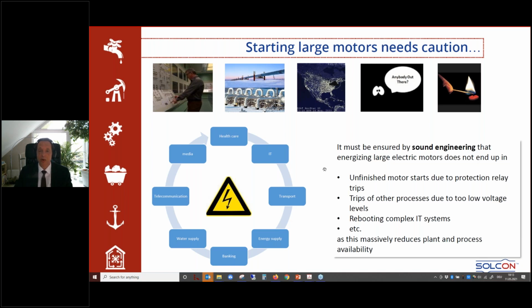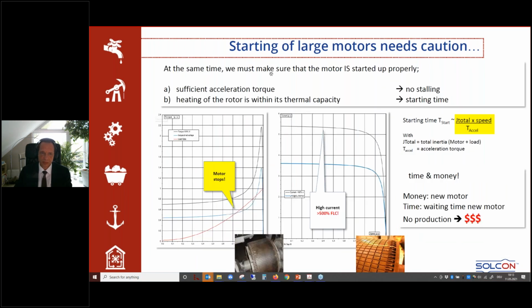So what we need to do, we need to apply sound engineering that we avoid unfinished motor starts due to protection relays tripping. We must avoid that processes are being tripped due to too low voltage levels, and rebooting complex IT systems is taking a very long time. And this reduces massively plant and process availability. So what to do? First of all, we need to make sure that we start up the motors properly. And we have two issues. One is we need to start up our process.